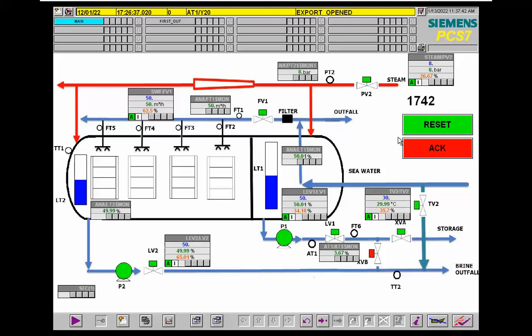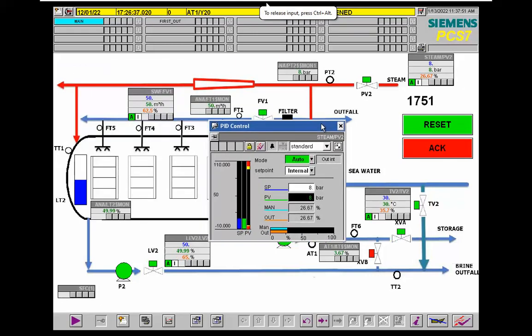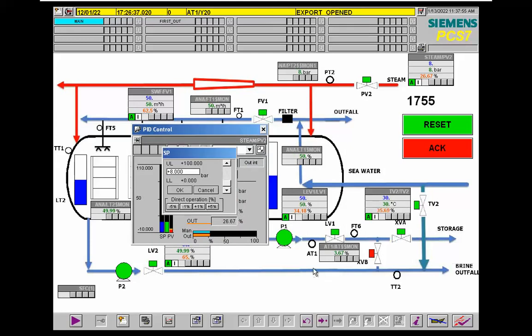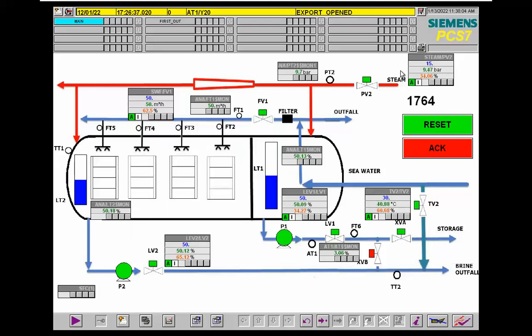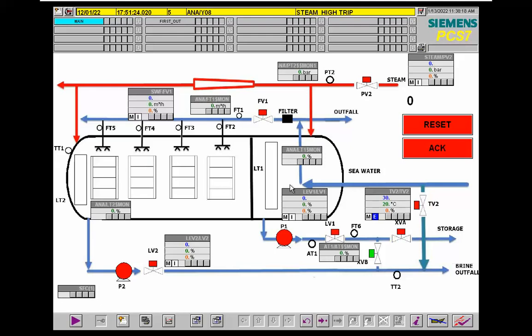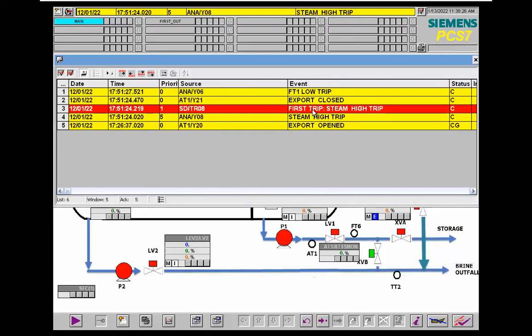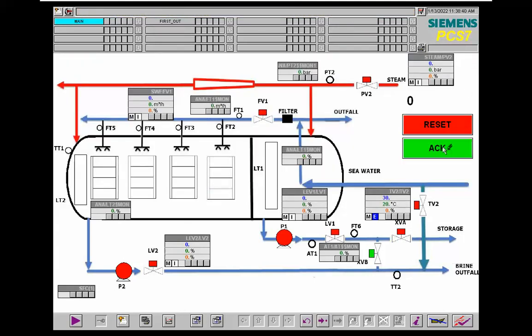It's a very simplified version. I will function test the over-pressure scenario. I will increase the set value to 15, and you can see that we have an increase when the steam pressure is increased based on the algorithm. Some other parameters in the plant are changing, but you can see we experience the high pressure trip due to steam high pressure, and the first trip-out is also reported here. Let me press acknowledge and start the whole process again.